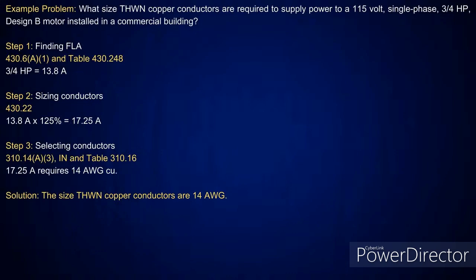So when you're looking at this, you would be looking over at 240.4G is where you're going to pick up your sizing for overcurrent devices, and these are going to be where you get over percentages that are over 125%. Okay. Right. So as we start to look at this is all going to tie in the same way. And the reason I bring up the overcurrent devices is because once I go to 240.4G, then I'm going to go look at 430.6A1. And you'll understand why I'm telling you this in just a second.